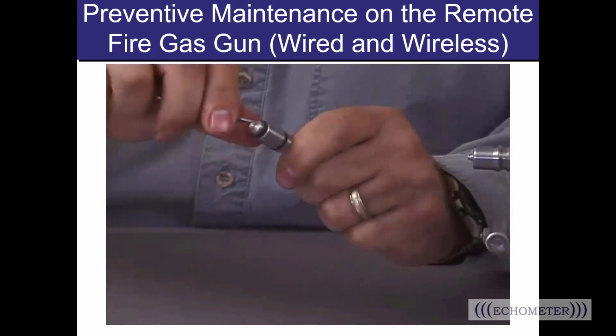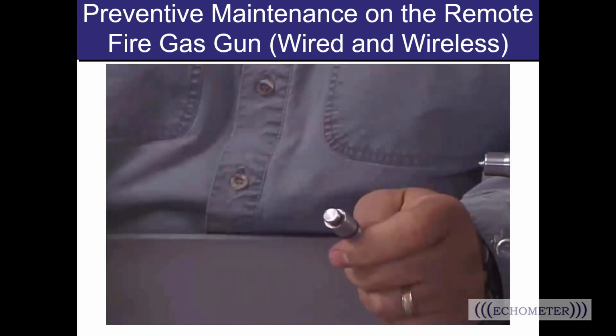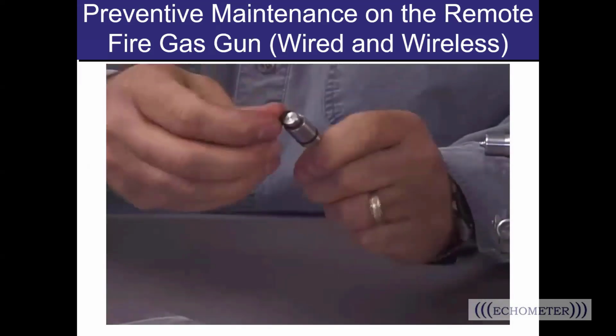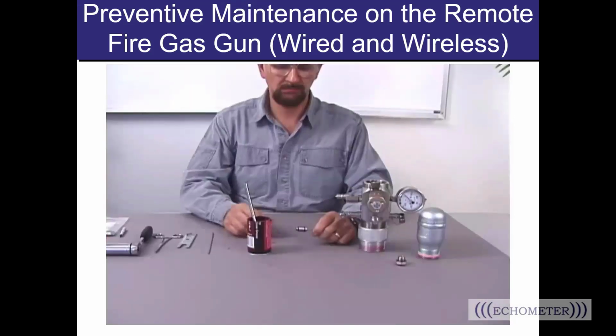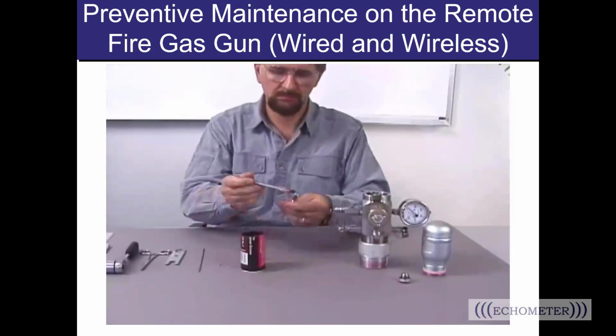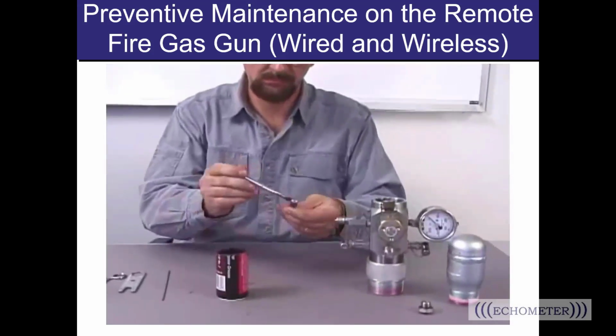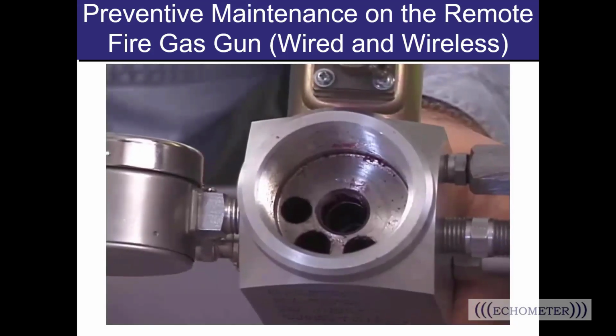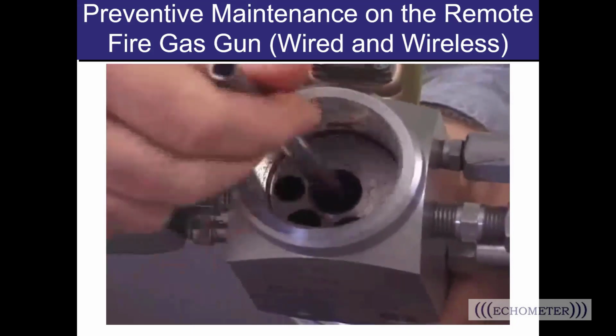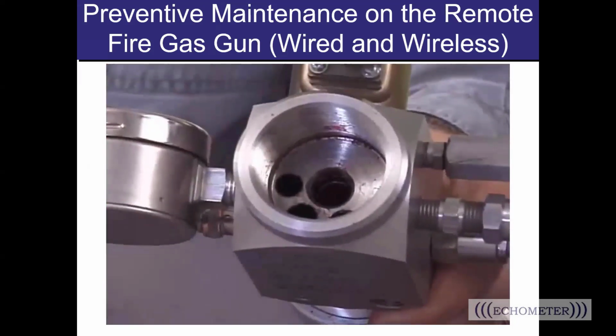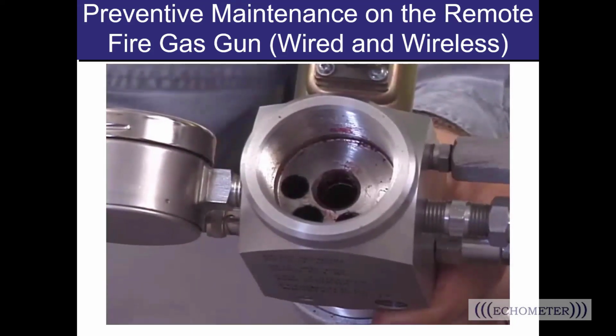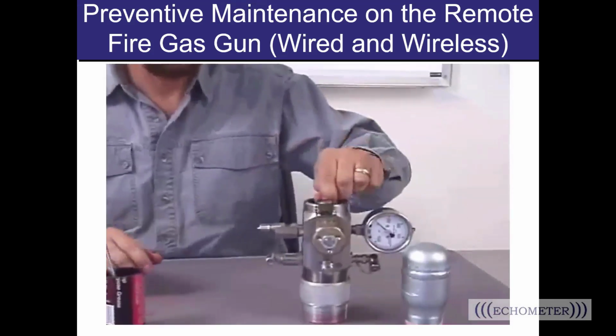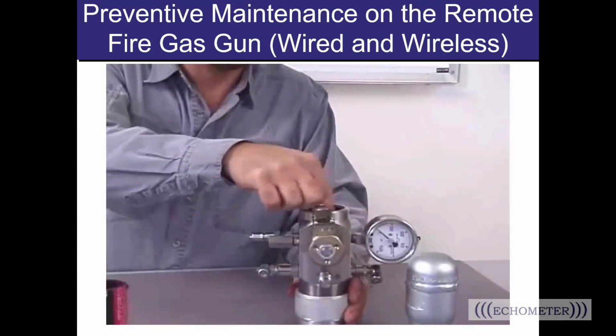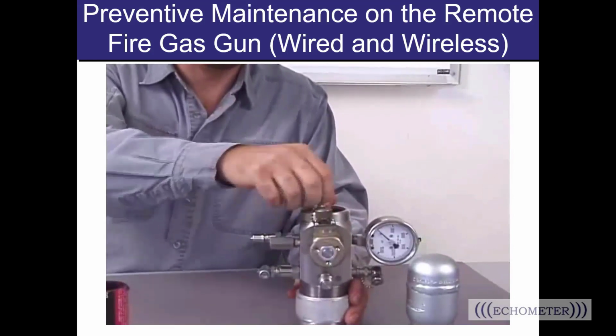So here you see I'm replacing that O-ring on the bottom of the gas valve, and that's the one that does the most work there. And you want to make sure that you're replacing it with the right O-ring. So all of our O-ring kits come with a little diagram just showing which O-ring and which part number. So again, you want to make sure you've got your drawing to make sure that you're putting the right O-ring on the part. Because there's a ton of O-rings in those little repair kit bags.